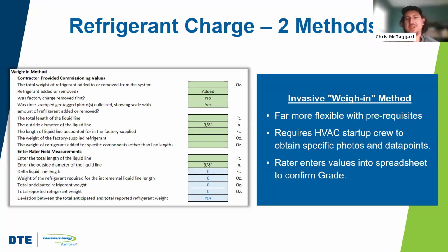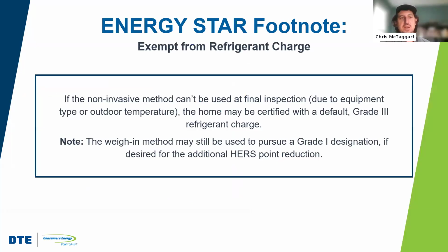So again, most raters are not competent to perform that test. And as a result, this is something that is allowed to be documented using photos and data points to be then provided to the rater to document a refrigerant charge. So these are the different methods that are allowed for documenting HVAC grading, which is a Track A option for HVAC installation verification for Energy Star.